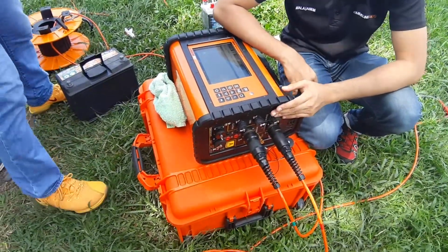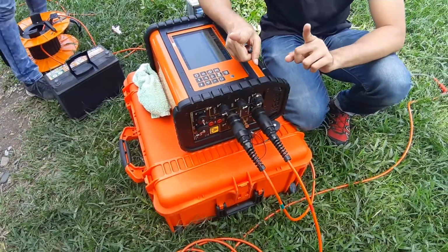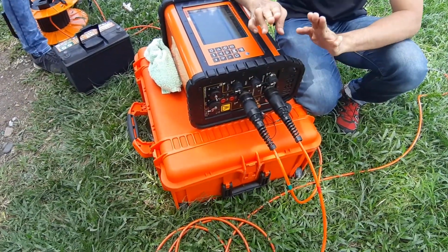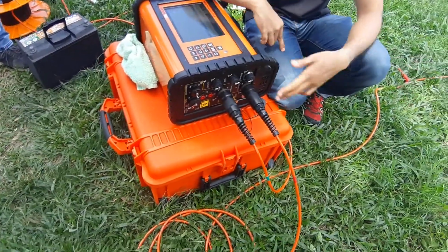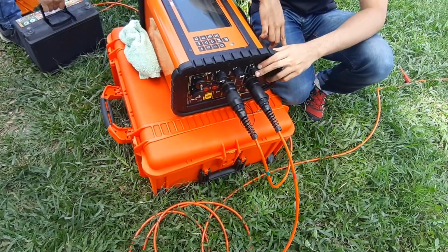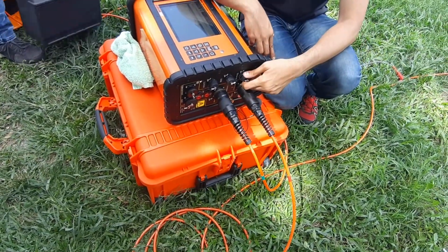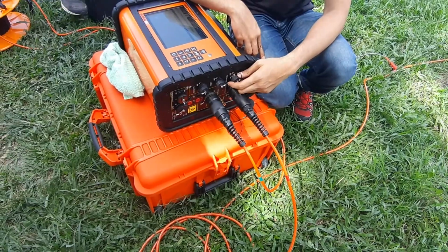So just now I mentioned that there is no overlap on this cable, because this type of cable is a 4x12. So you just lay it all the way, no overlapping. 4x21 is the overlapping cable.